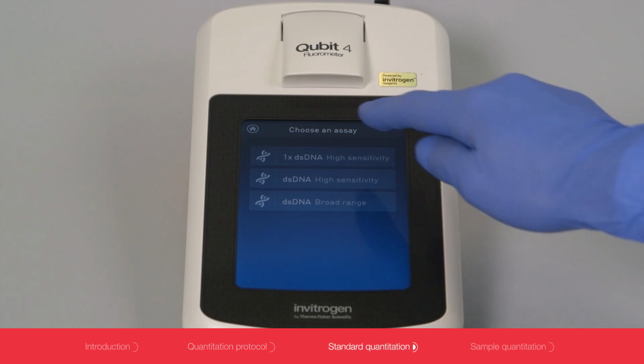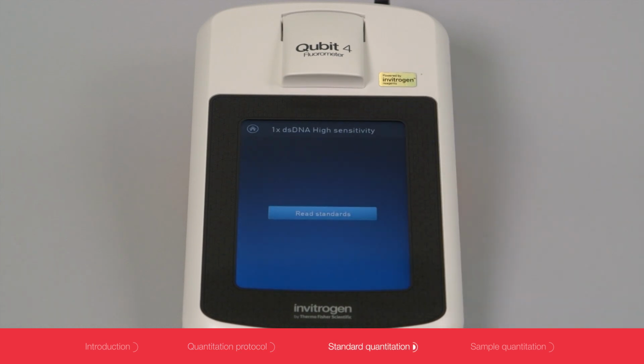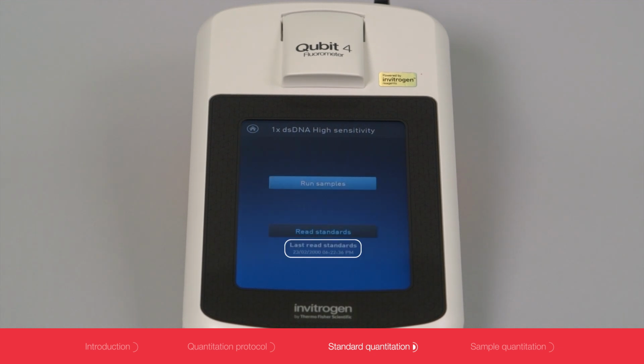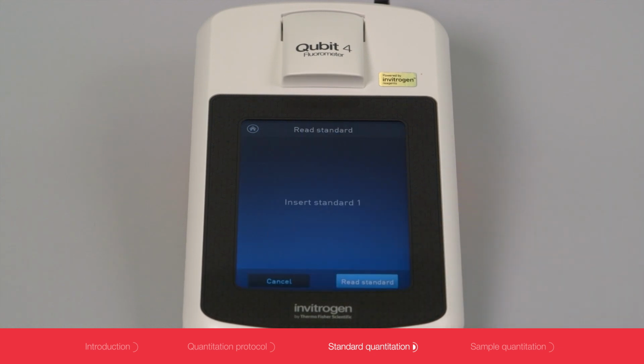The first time you run an assay, you will only see Read Standards. The instrument will save the standards with a time and date stamp. For subsequent assays, you can choose whether to use the saved standards or run a new standard calibration.